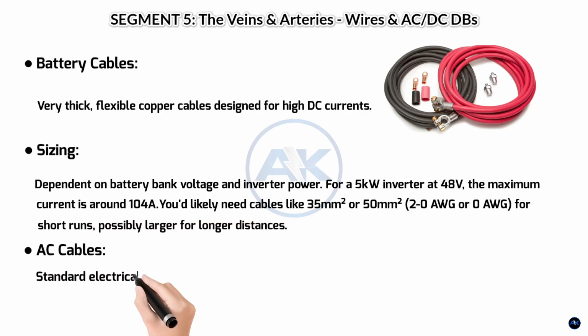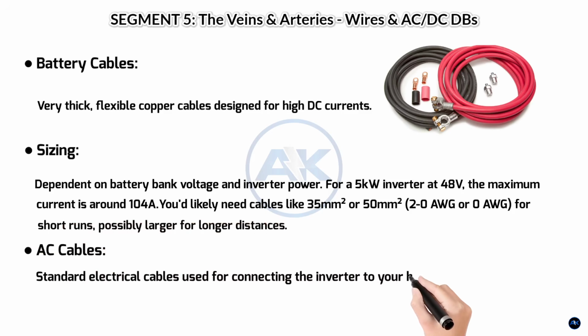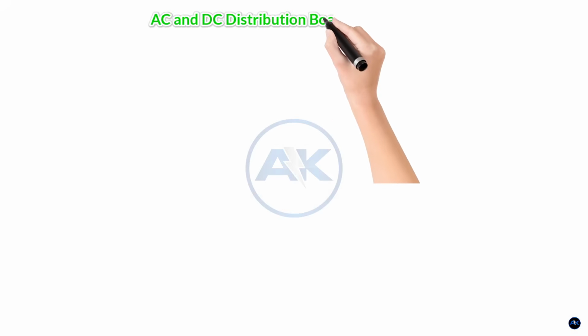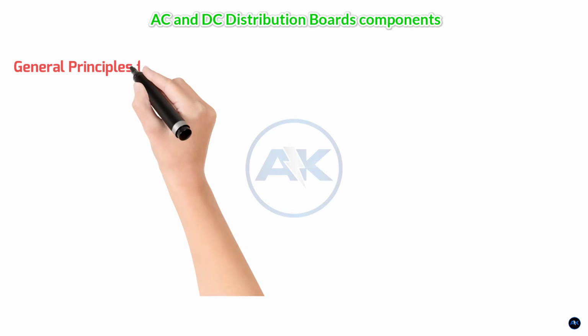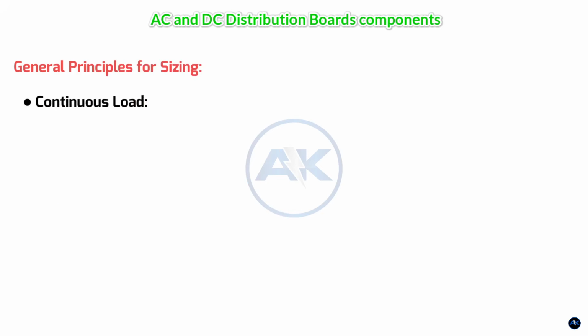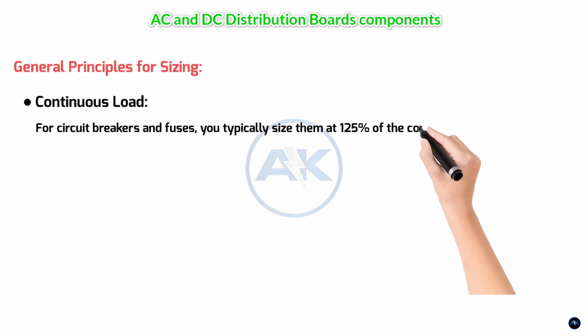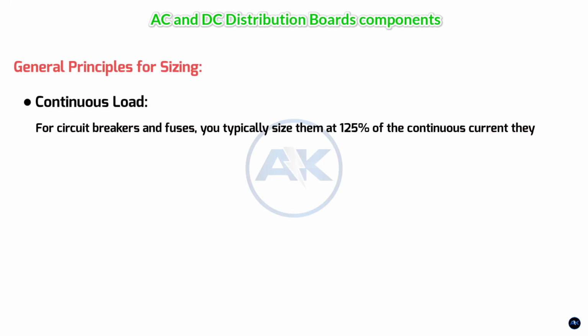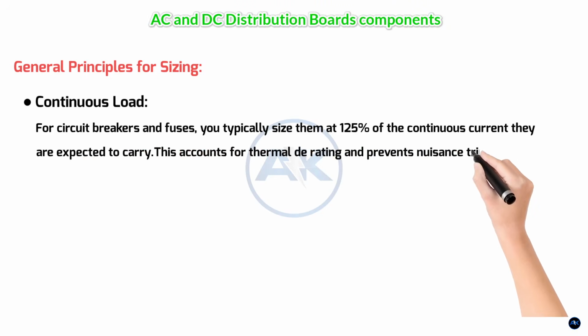AC cables: standard electrical cables used for connecting the inverter to your home's main distribution board and the grid. Sizing of the critical components in both your AC and DC distribution boards for a 5 kilowatt hybrid solar system. General principles for sizing: continuous load. For circuit breakers and fuses, you typically size them at 125% of the continuous current they are expected to carry. This accounts for thermal derating and prevents nuisance tripping.